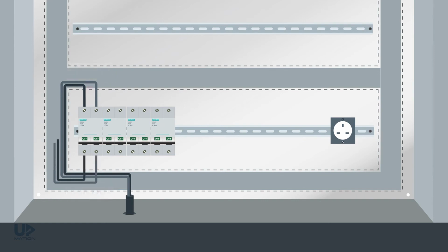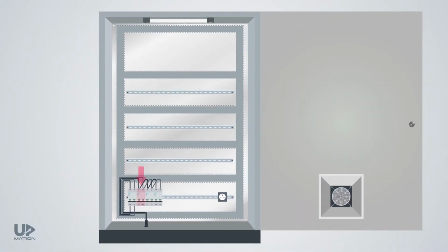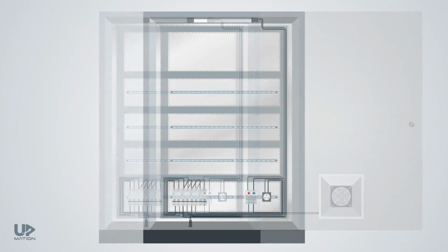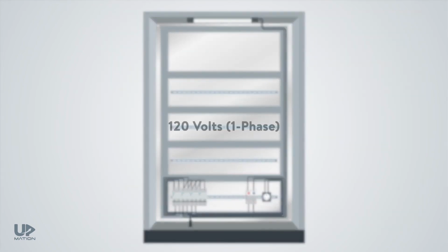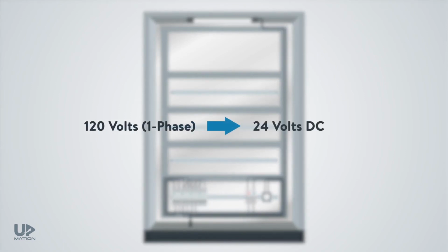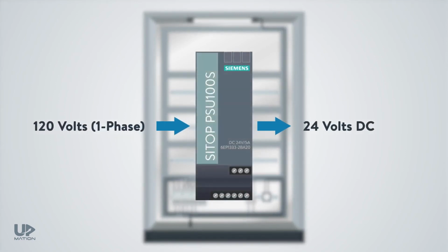So, I take the power from the main MCB and connect it to the input of the other MCBs. This one is for the socket and the lamp. This one is for the fan. And this is for the control's power supply. To step the power down from single-phase 120 volts to the control voltage, which is 24 volts for example, we need a 24 volts power supply with an appropriate amperage capacity.